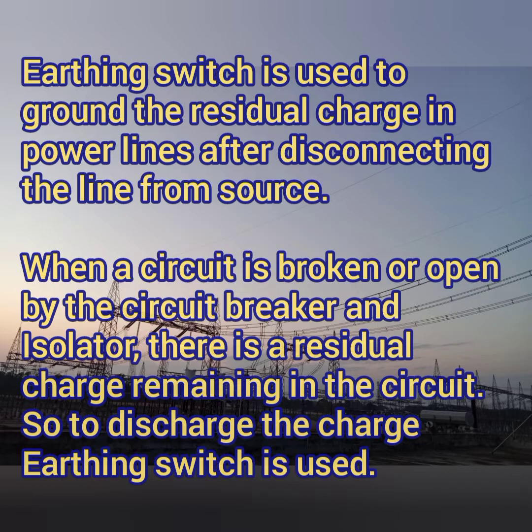Normally, the earth switch is used in your substation to ground the residual charge in your power line after disconnecting the line from the source. When a circuit is broken or opened by the circuit breaker or the isolator, there is a residual charge remaining in the circuit. In order to discharge that charge, the earth switch is used.